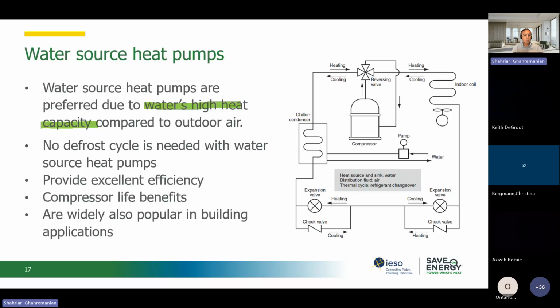The other benefit of the water source heat pump is that we don't need a defrost cycle. In a winter season, the air source heat pumps work, and because of the humidity that might exist, we need to defrost the cycle, which takes some energy, because the system shuts down itself, goes through the mode of defrosting, and then comes back. So during that time, we don't have any heating and cooling. The other thing is that it uses energy. So that is not good.